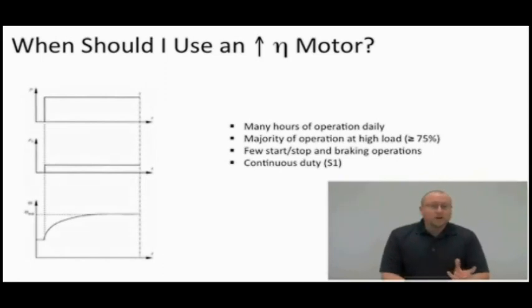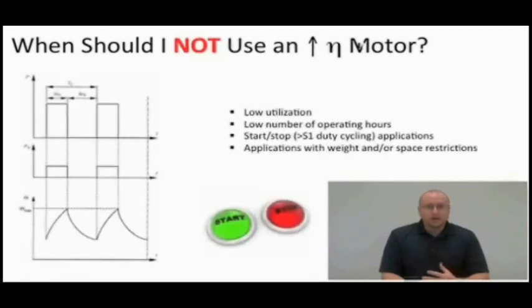So now that we know when to use an energy efficient motor, when do we not want to use one? Well, the exact opposite. If the utilization is bad, like if the motor is really underloaded, if you're starting and stopping the motor all of the time, or if you have a low number of operating hours. If you only run this motor for 15 minutes, a half an hour, or an hour a day, when are you going to end up gaining the money back that you put into the initial cost of the motor? Well, it's going to take a long time for the amortization to occur, and it's not going to be worth it for you. So you also need to know when you shouldn't use an energy efficient motor.